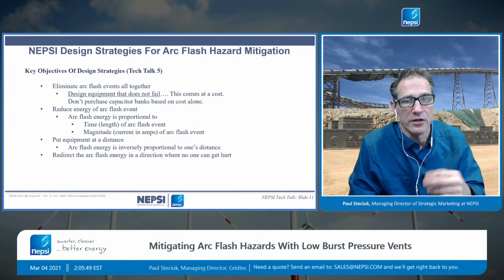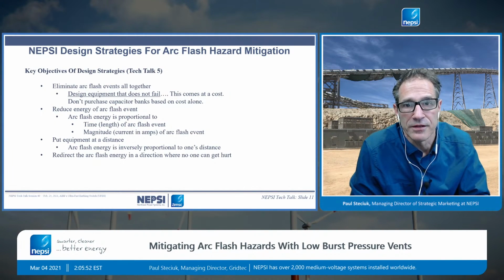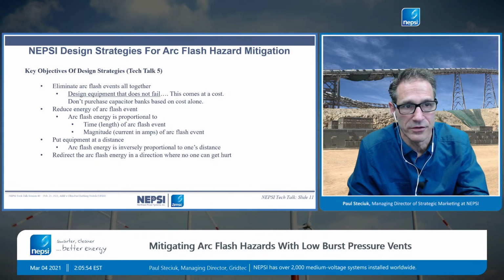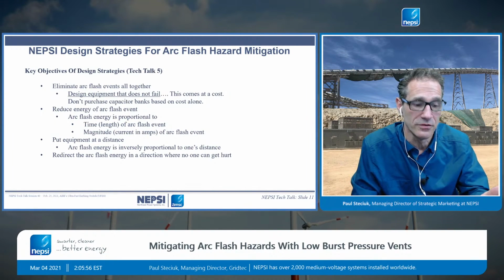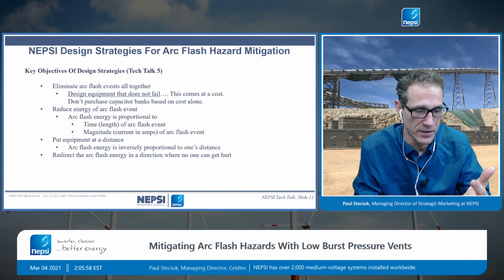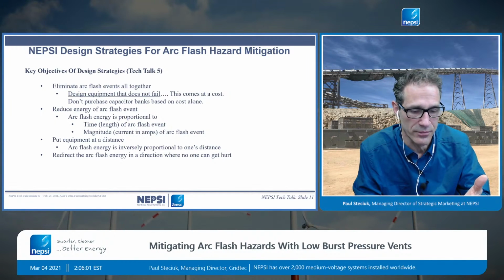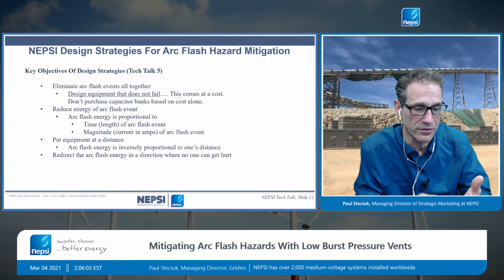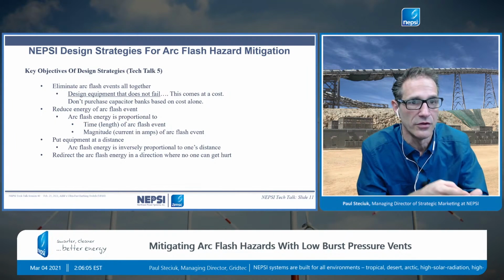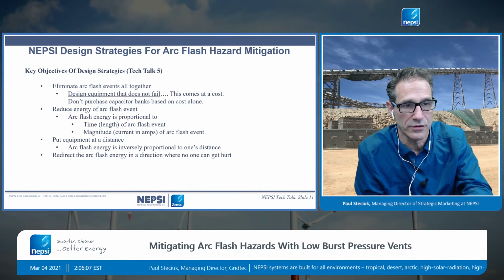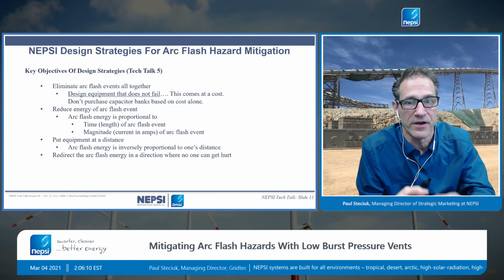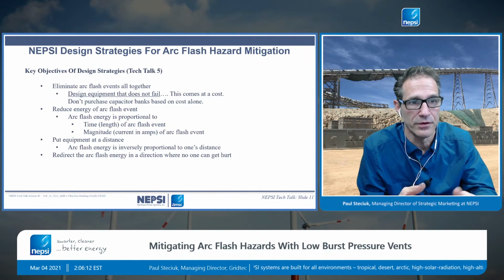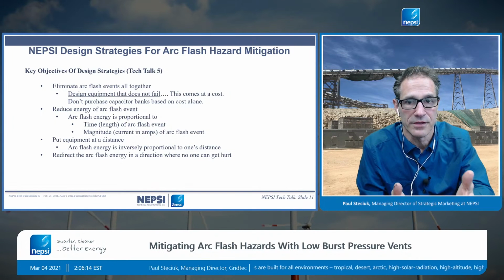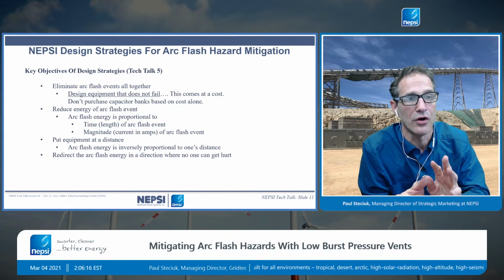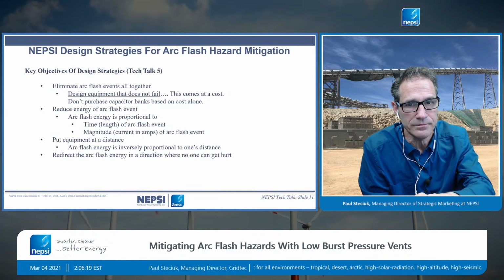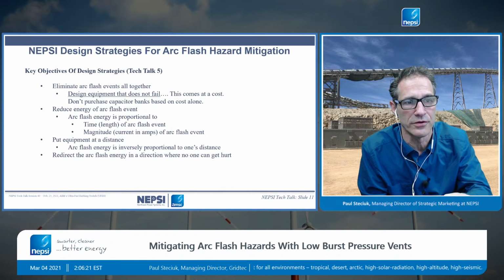Remember we were talking about eliminating arc flash events. First of all, design equipment that doesn't fail. There's lots of things you can do. You can increase the insulation level. You can do more testing to make sure it's designed properly. You can insulate bus bars. You can put current limiting fuses in there. You can speed up protection. You can put the ultra-fast earthing switch in there. And then finally, there's a possibility of putting a passive technique of actually sending the arc out the back of the enclosure. And that's what we're talking about today, a low burst vent.